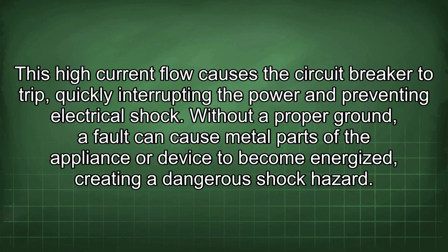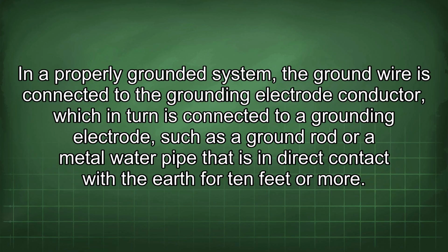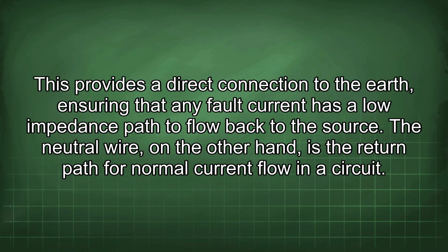Without a proper ground, a fault can cause metal parts of the appliance or device to become energized, creating a dangerous shock hazard. In a properly grounded system, the ground wire is connected to the grounding electrode conductor, which in turn is connected to a grounding electrode, such as a ground rod or a metal water pipe that is in direct contact with the earth for 10 feet or more.